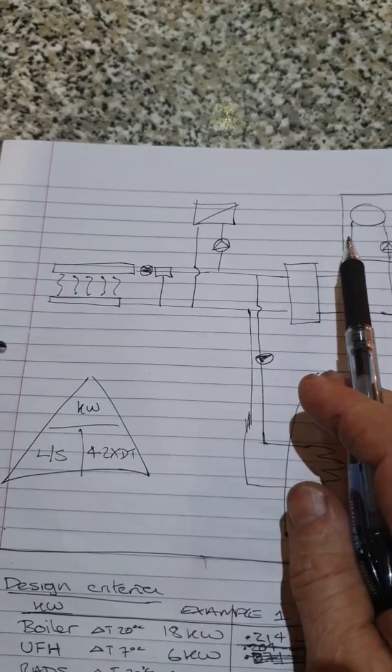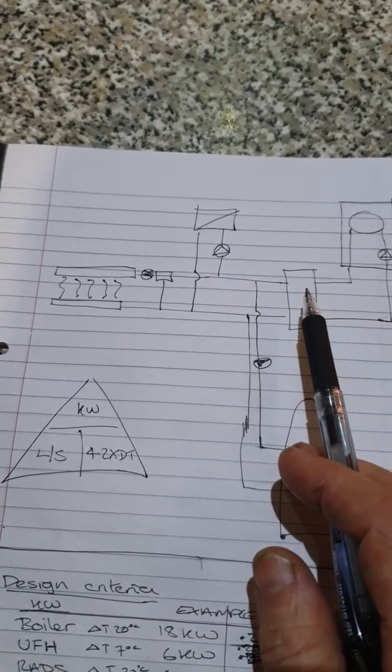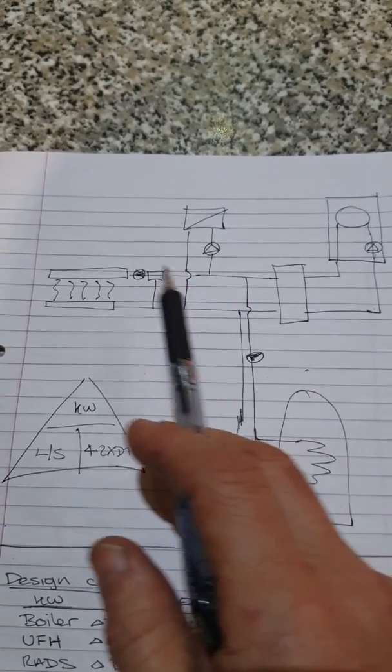The long-term fix is to put in hydraulic separation and let the boiler run at lower temperature, curing the flow rate problem through the low loss header.